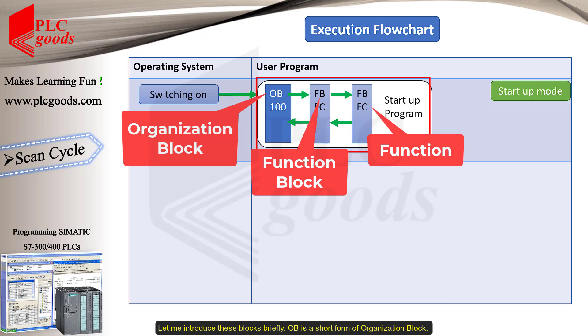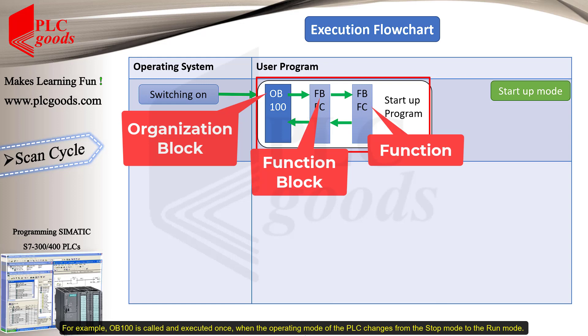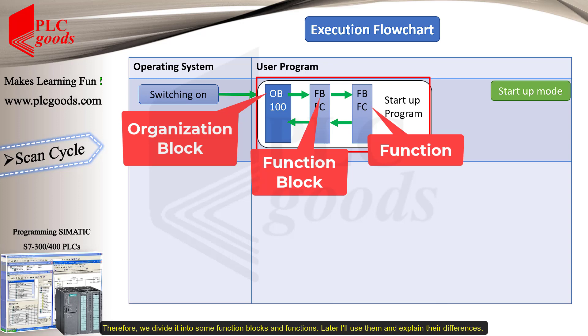Let me introduce these blocks briefly. OB is a short form of organization block. It represents the interface between the operating system and the user program. The operating system can only call organization blocks for specific events. For example, OB 100 is called and executed once when the operating mode of the PLC changes from the stop mode to the run mode. Usually, the user program is long and complex, especially for industrial purposes. Therefore, we divide it into some function blocks and functions. Later, I'll use them and explain their differences.